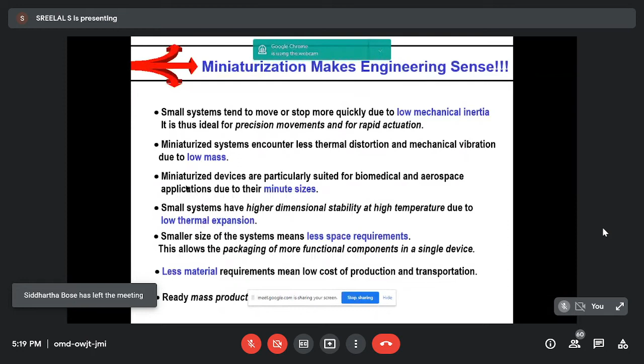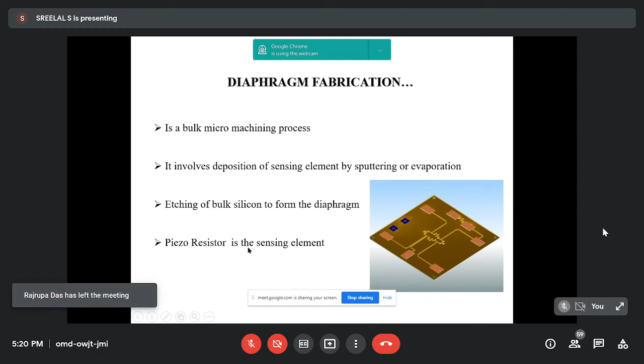So how do we fabricate? Earlier in the case of pressure sensors, we said that there is a metallic diaphragm. So how do we fabricate this diaphragm? It is done using a process called bulk micromachining. It involves deposition of the sensing element by sputtering or evaporation, then etching of bulk silicon to form the diaphragm, and the piezoresistor is the sensing element which is used in these pressure sensors.